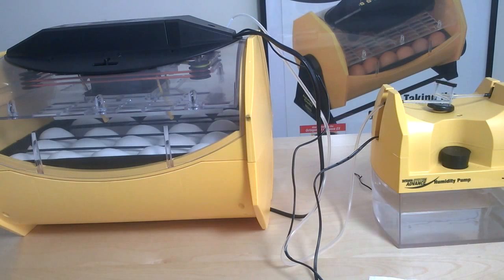The other thing to note is that the pump will only operate if the incubator is operating above the minimum temperature alarm setting on the machine. The reason it does that is to prevent the pump from adding too much water if, for example, the lid has been taken off, or if, for example, you're using the cooling. So the pump will only operate if you're close to the target temperature.